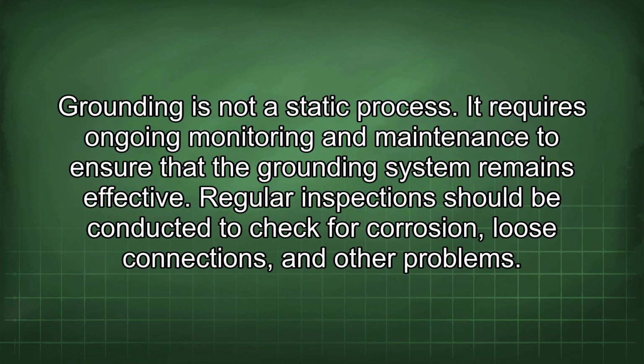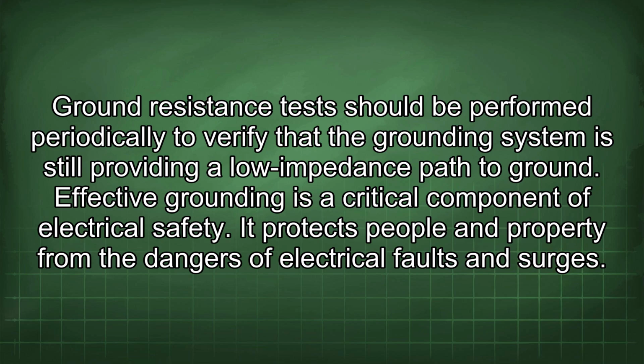Grounding is not a static process. It requires ongoing monitoring and maintenance to ensure that the grounding system remains effective. Regular inspections should be conducted to check for corrosion, loose connections, and other problems. Ground resistance tests should be performed periodically to verify that the grounding system is still providing a low impedance path to ground. Effective grounding is a critical component of electrical safety.